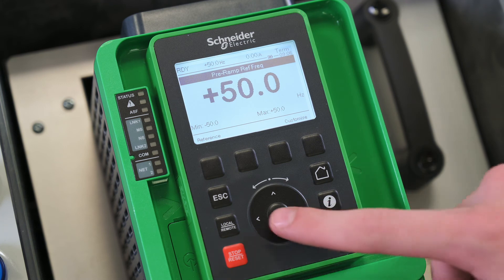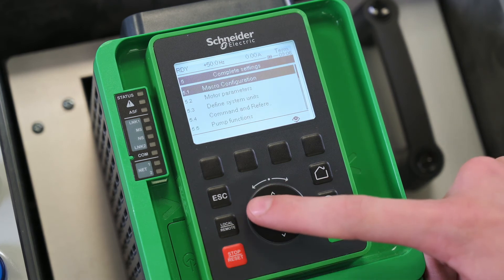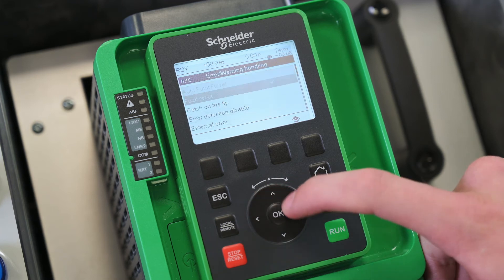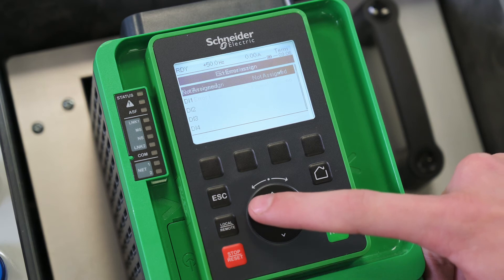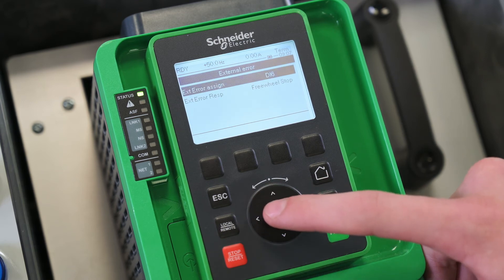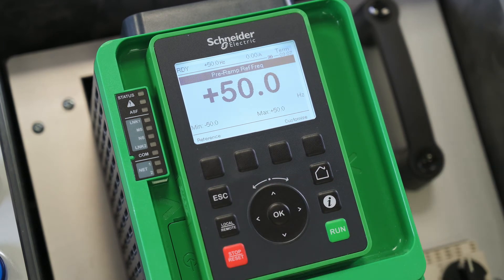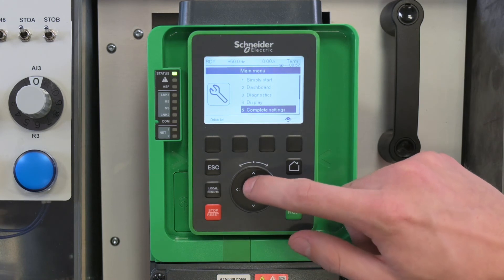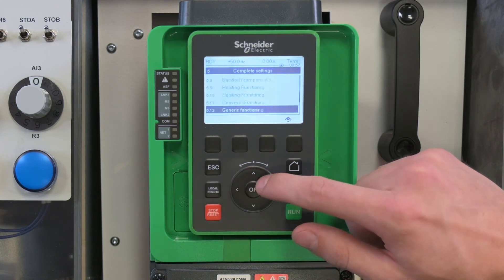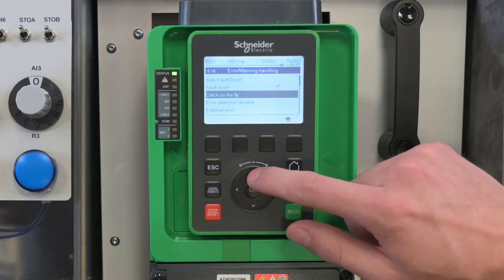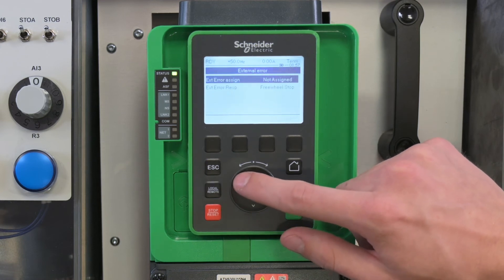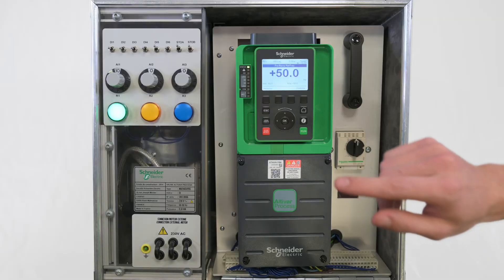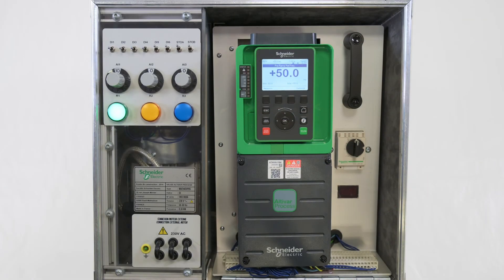We are going to make a test by assigning an external error to DI6 to show that this error is not detected if INH is activated. By activating DI5, the error detection is disabled. If you activate DI6 to trigger an external error, the error is not triggered.